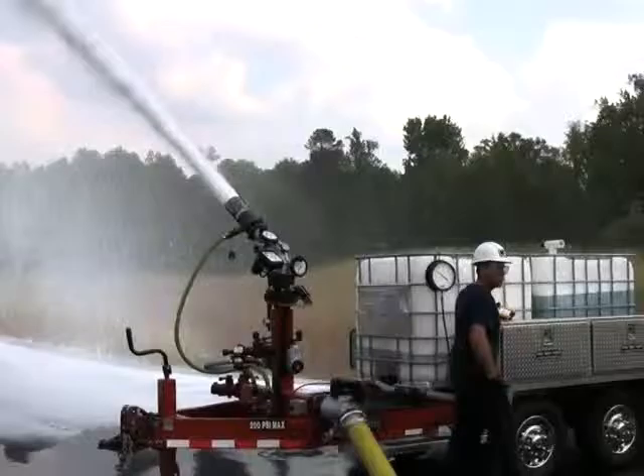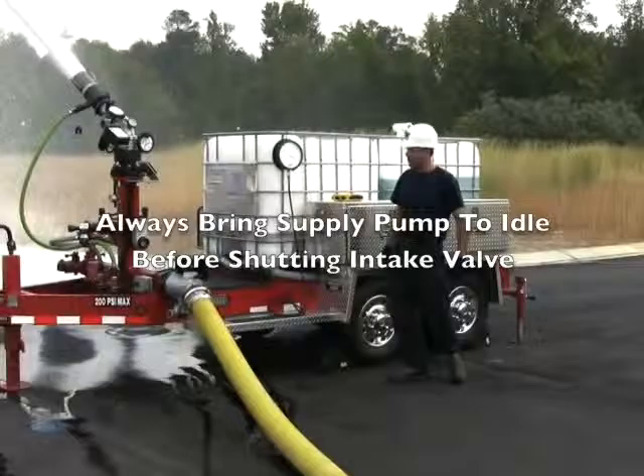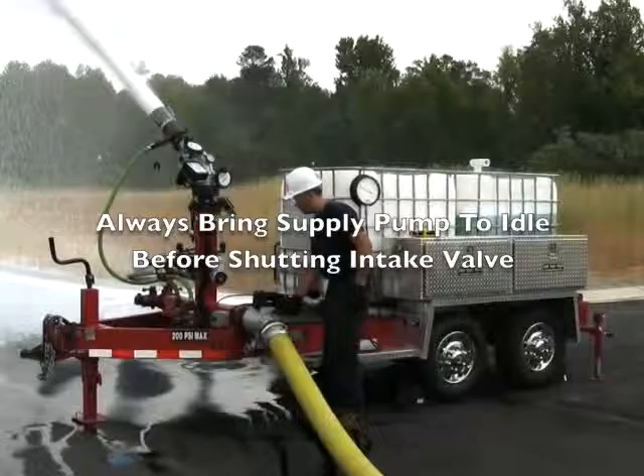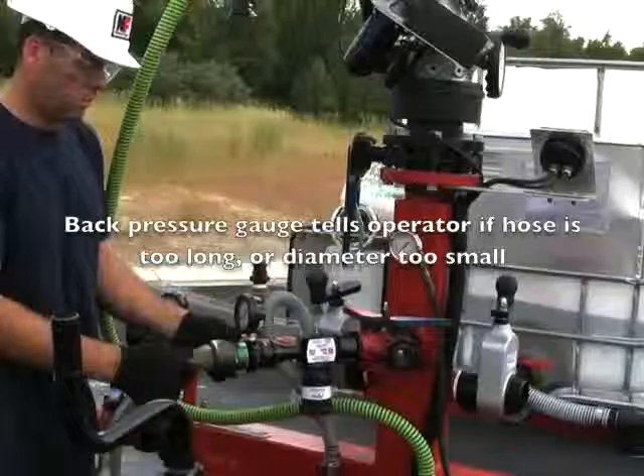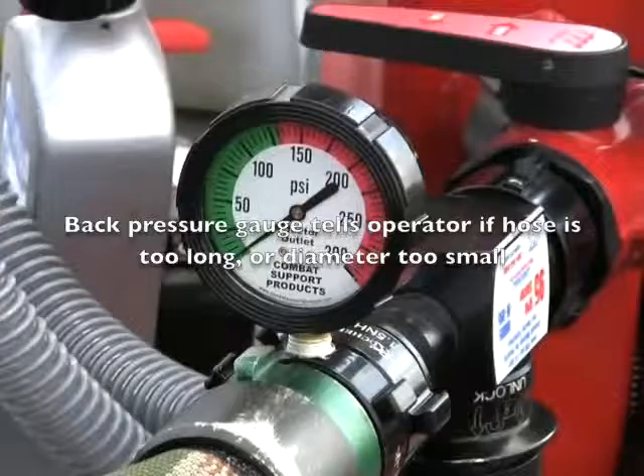Now Dan's going to go through the shutdown procedure. He signals to the driver operator to bring the engine to idle, and then he closes the intake valve. Now Dan's going to make an inch and three-quarter hose connection at the TFT foam eductor. Notice we have a pressure gauge on the outlet of this foam eductor, and that little pressure gauge is going to tell us whether or not we have a go or no-go situation when it comes to foam concentrate proportioning.